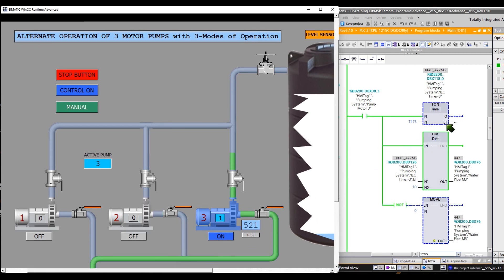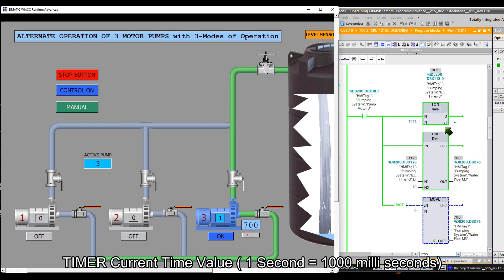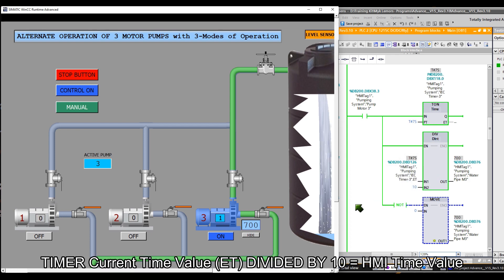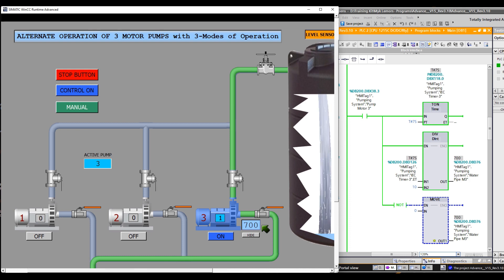When the pump is on, the time-on-delay timer is also on. ET, or the current time value — 1 second is equivalent to 1000 milliseconds. But using this division instruction block, I divide ET by 10 to make the digit smaller on the HMI screen. So 7 seconds is now equivalent to 700 milliseconds on the HMI after using the division instruction block.